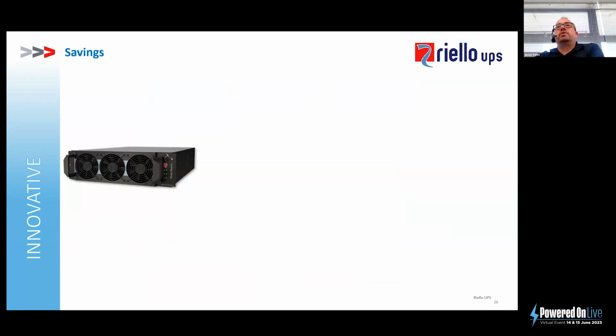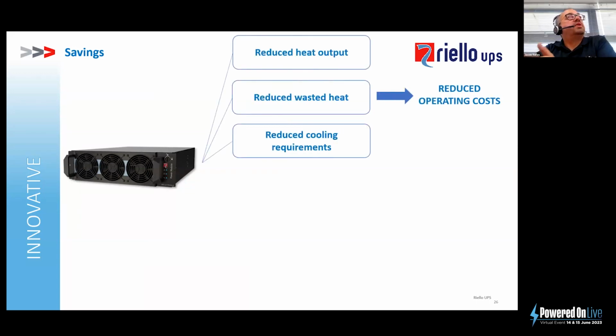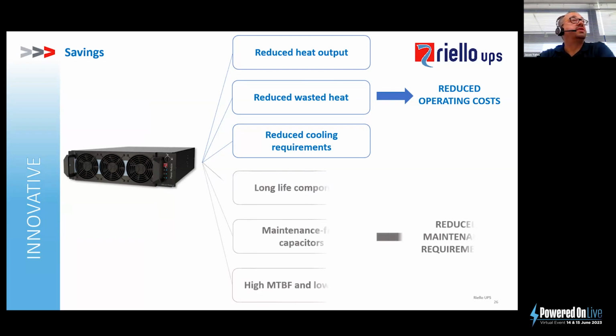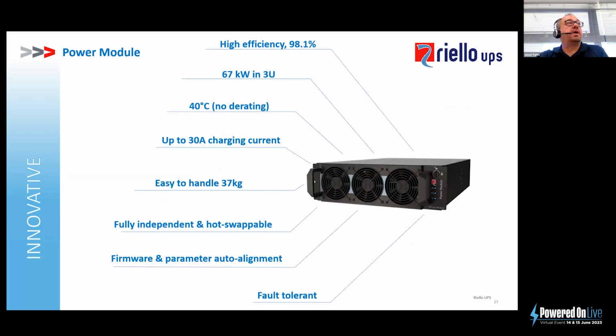So what savings could be achieved from this? Well, basically, because there is reduced heat output, reduced wasted heat, and reduced cooling requirements, obviously our operating costs are going to come down. In addition to this, because we're using long life components, maintenance-free capacitors, and we have a high MTBF, which is effectively mean time between failures, and a low MTTR, which is mean time to repair, we reduce our overall maintenance costs.